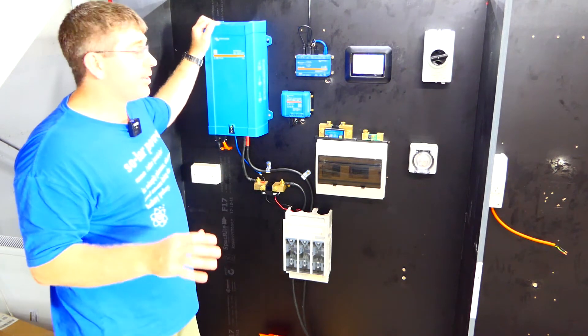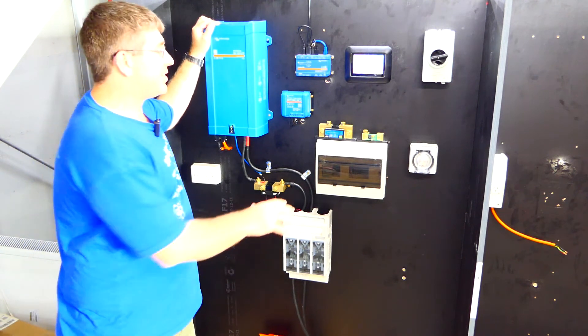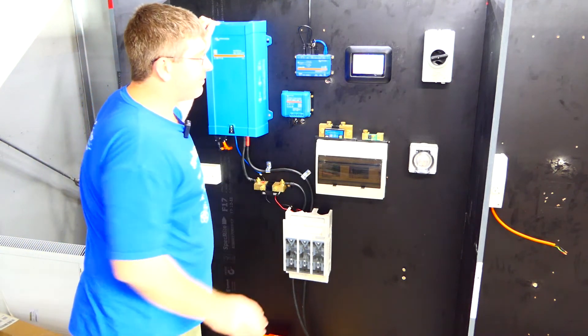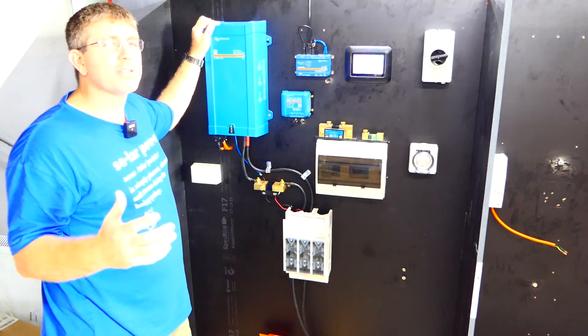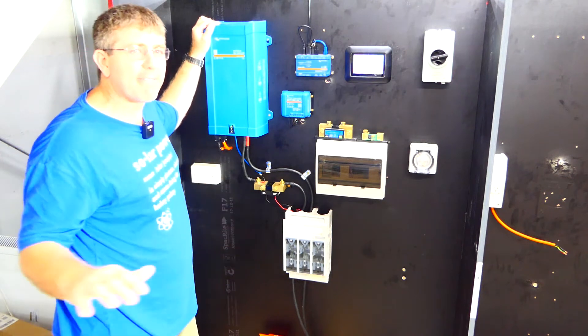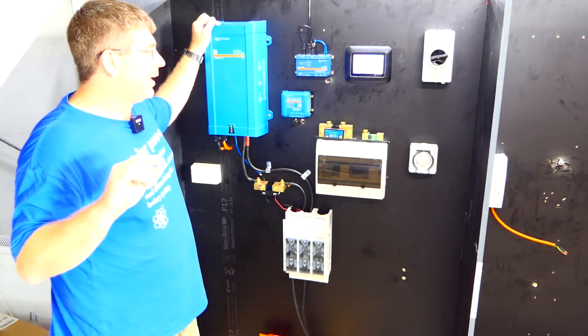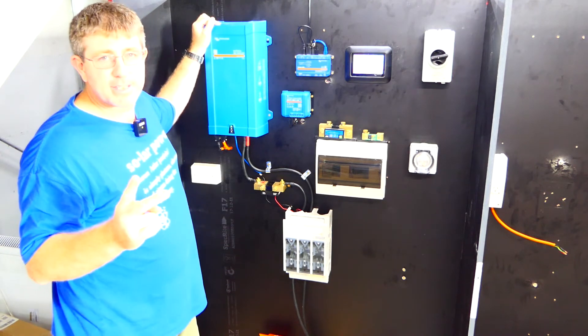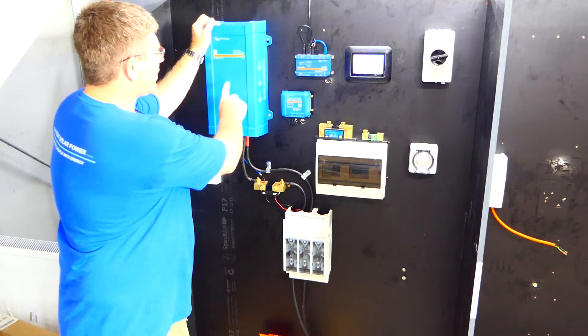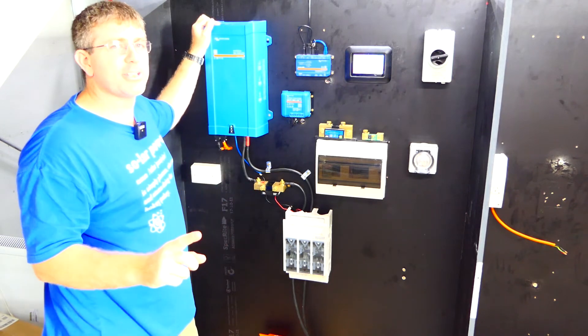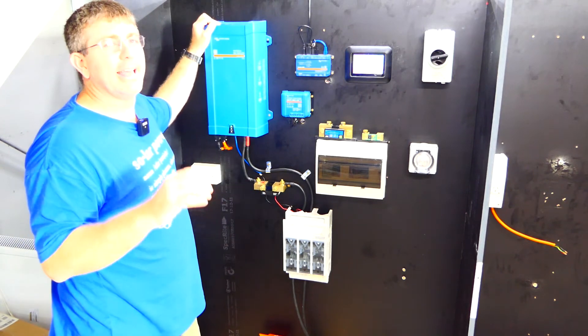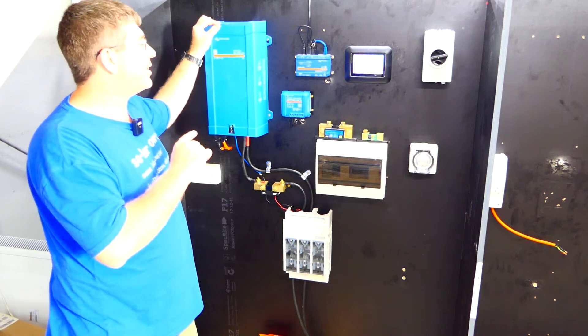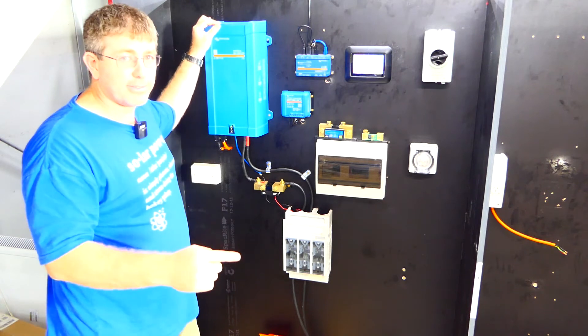Now the next thing I highly recommend is to get yourself one of the Victron Smart Shunts. Now the reason we, for us as a business, we install these in every single system that we do for two reasons. One is if you don't have a smart shunt or a battery monitor, the inverter doesn't see what energy it uses itself.